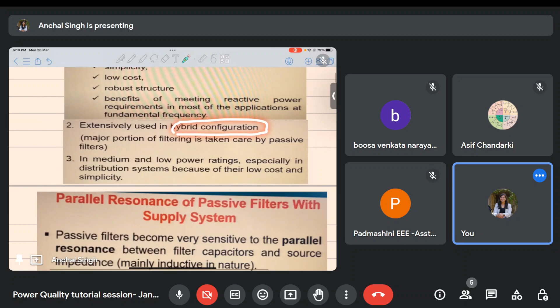So there is one big problem with passive filters, and that is the problem of resonance. Resonance occurs when all the inductive reactive power present in my system is compensated by all the capacitive reactive power. When both of these reactive powers become equal, they cancel out each other, leaving only the resistive element in the circuit.